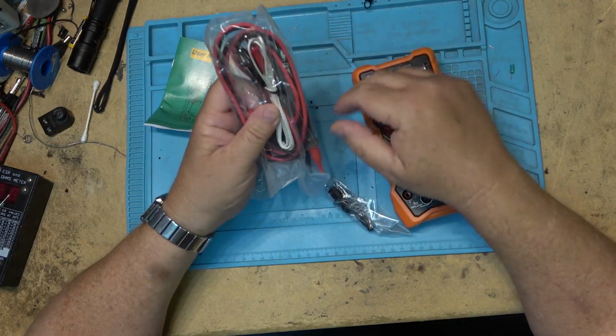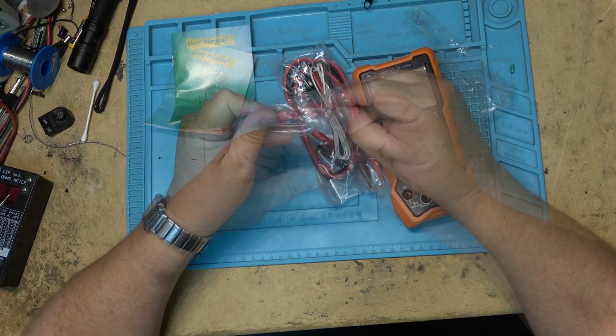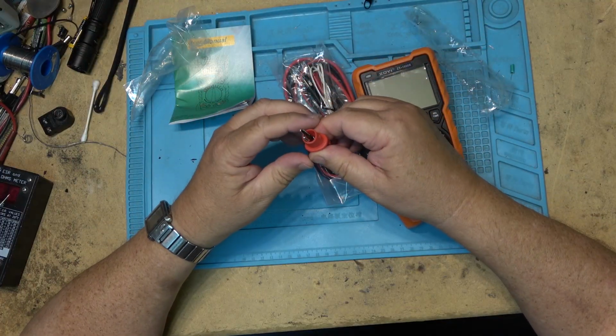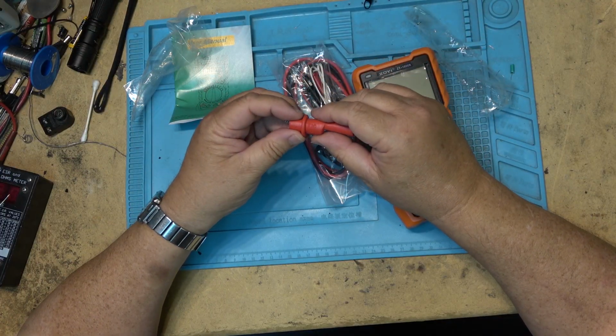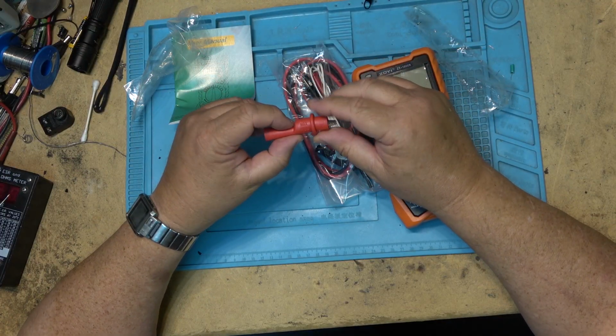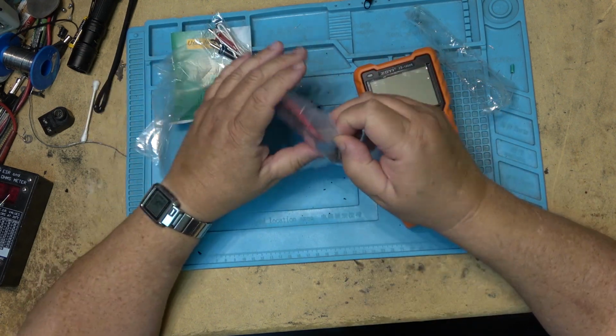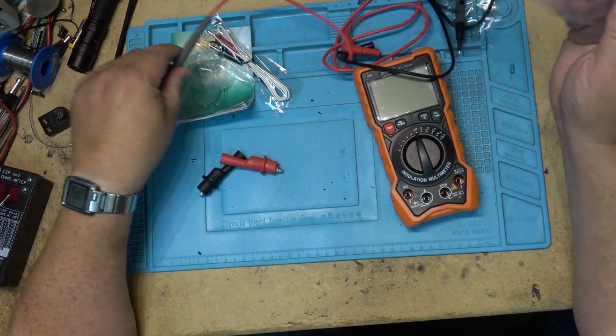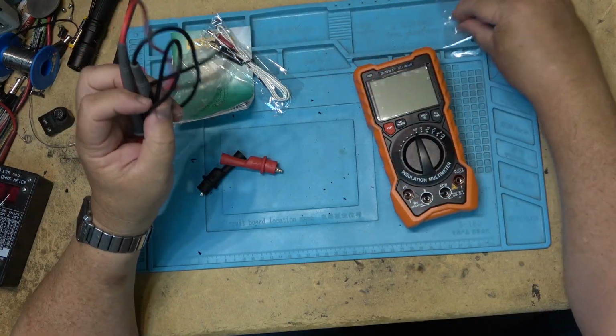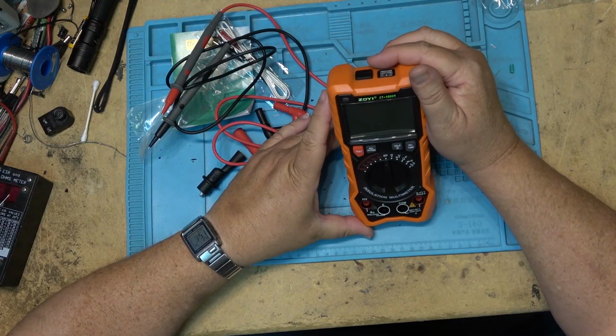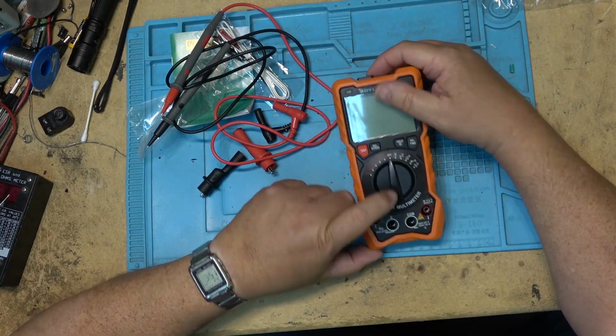Comes with the usual stuff. It's got these nice clips that you can clip on, and they provide good insulation. 1,000 volts is the rating on the insulation here. Temperature probe, and of course the regular measurement probes. This is called an insulation multimeter. So let's look at the specifications, see what exactly it does.